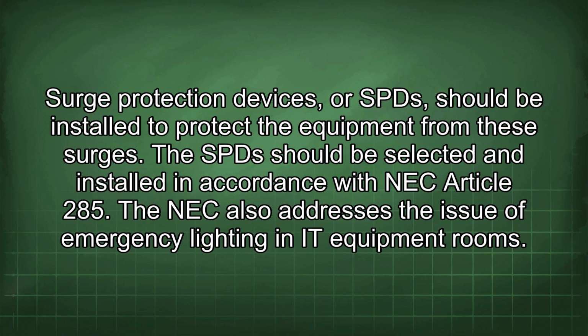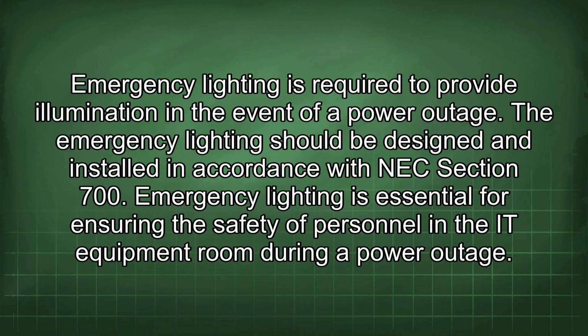The NEC also addresses the issue of emergency lighting in IT equipment rooms. Emergency lighting is required to provide illumination in the event of a power outage. The emergency lighting should be designed and installed in accordance with NEC Section 700. Emergency lighting is essential for ensuring the safety of personnel in the IT equipment room during a power outage.